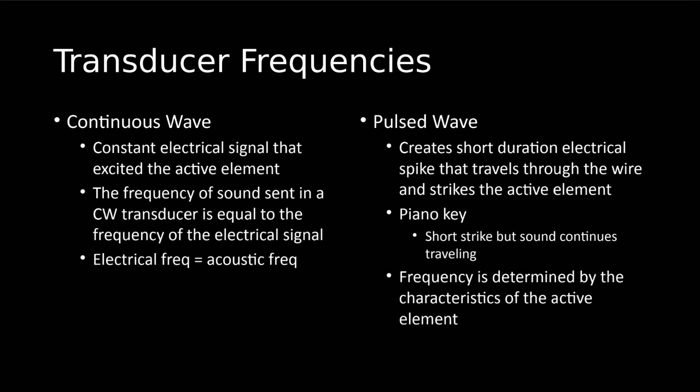Okay, so our transducer frequencies. So everything that we've learned so far has always kind of been geared towards pulsed wave, right? We haven't talked too much about continuous wave, but what we know about continuous wave is that it's constantly going, right? There's no talking, there's no listening. It's just always talking and always receiving. So we don't use that because that's not the best in order for us to get and process those reflections. We need the talking time and we need the listening time.